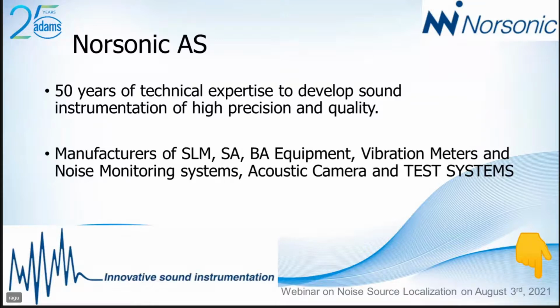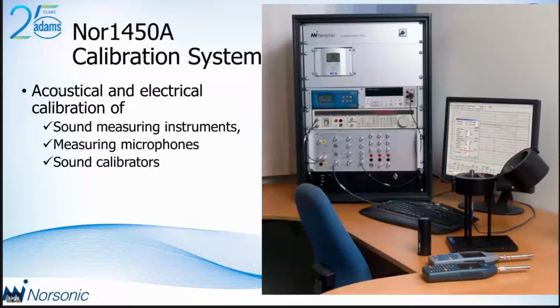So again, we'll get back to today's topic, calibration system. We have a calibration system from Norsonic. This allows you to perform acoustical and electrical calibration of sound level meters, microphones, sound calibrators, and any related sound measuring equipment. So this is the complete system in itself. It has a PC and software. It has a barometer, hygrometer. It also has a DC power supply. It has a small chamber for the microphone calibration, and for the level calibration, it has the pistonphone here.